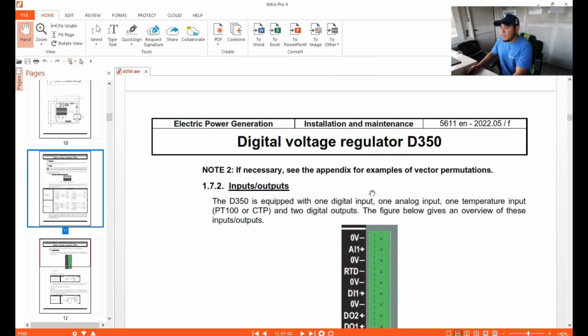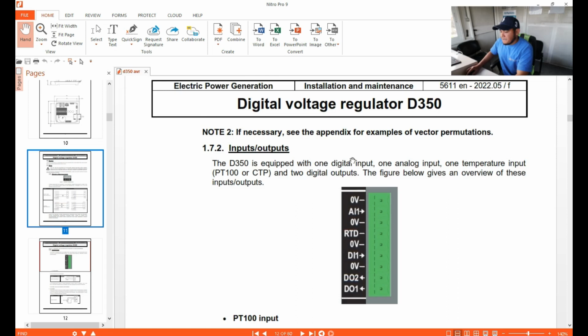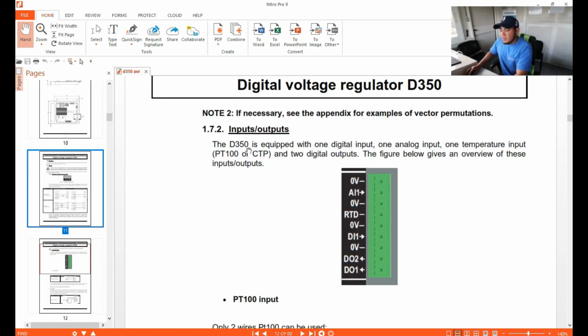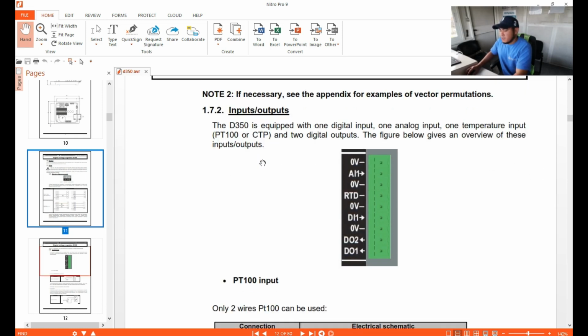So let's jump up here to our digital voltage regulator. This is what we call the inputs and outputs. Okay, the D350 is equipped with 1 digital input, 1 analog input, 1 temperature input, as I told you, where we can install the sensor which we call the PT100, and 2 digital outputs. The configuration below gives you an overview of the inputs. Okay, these are all the connections you can use for the options you need.